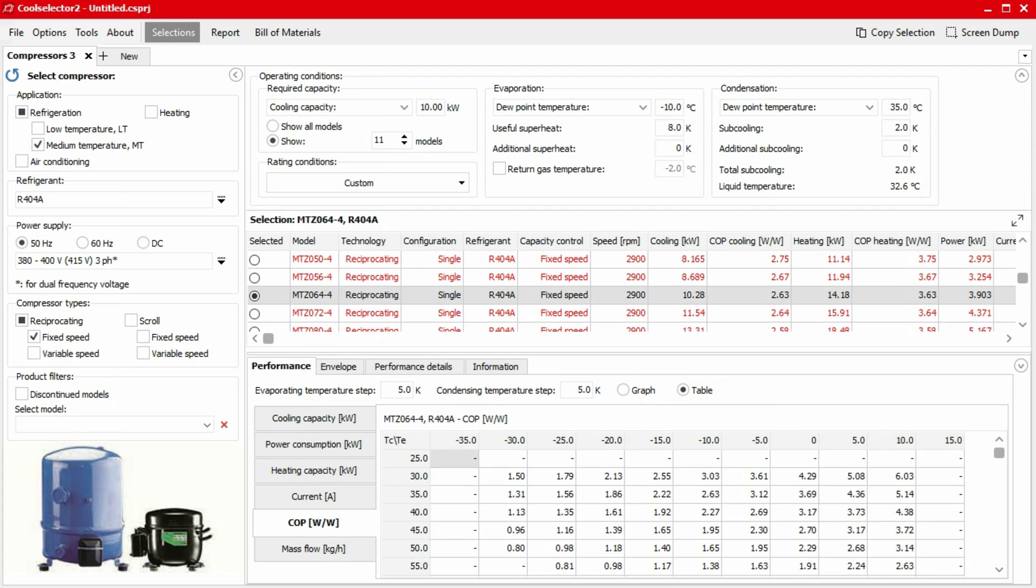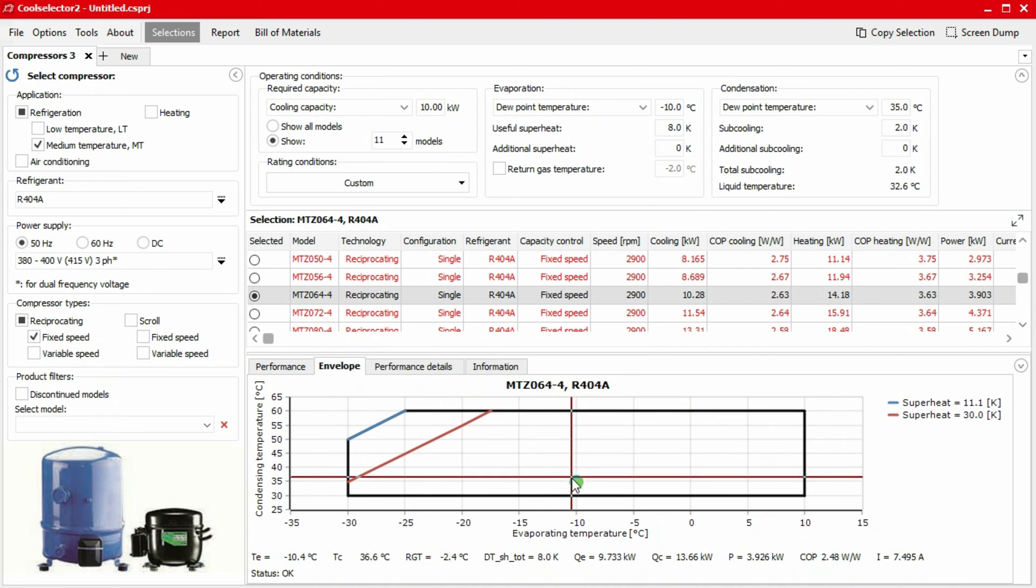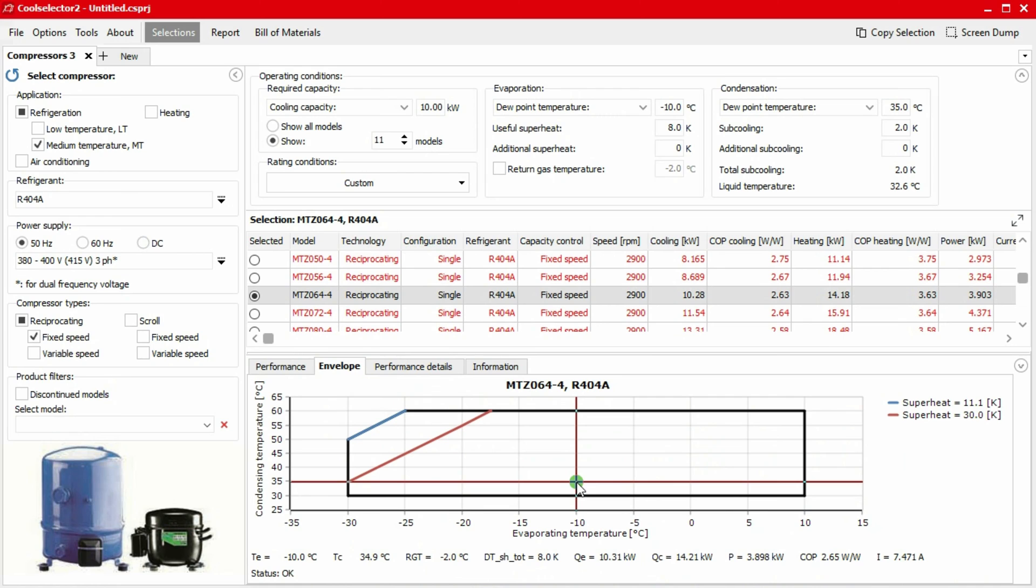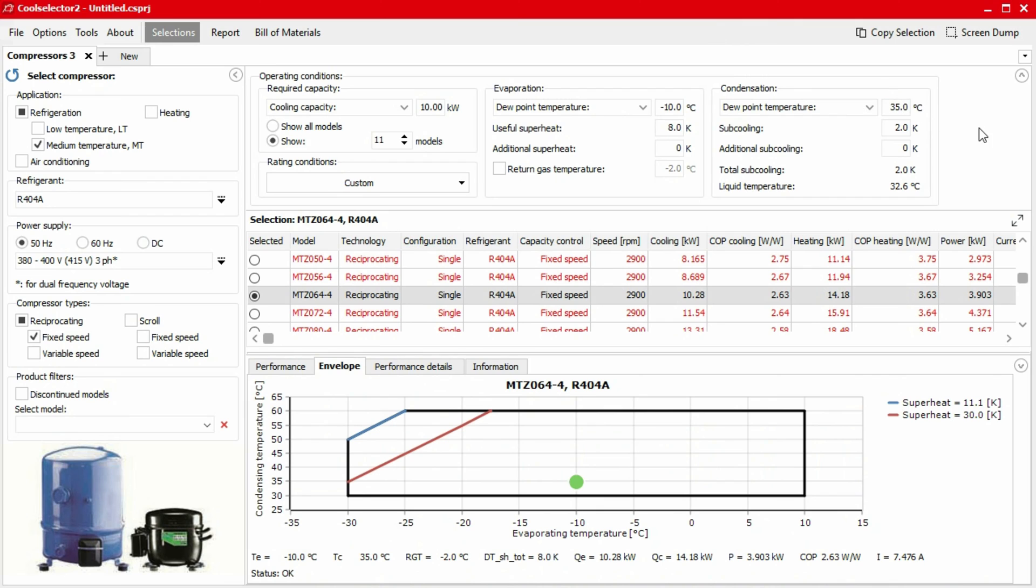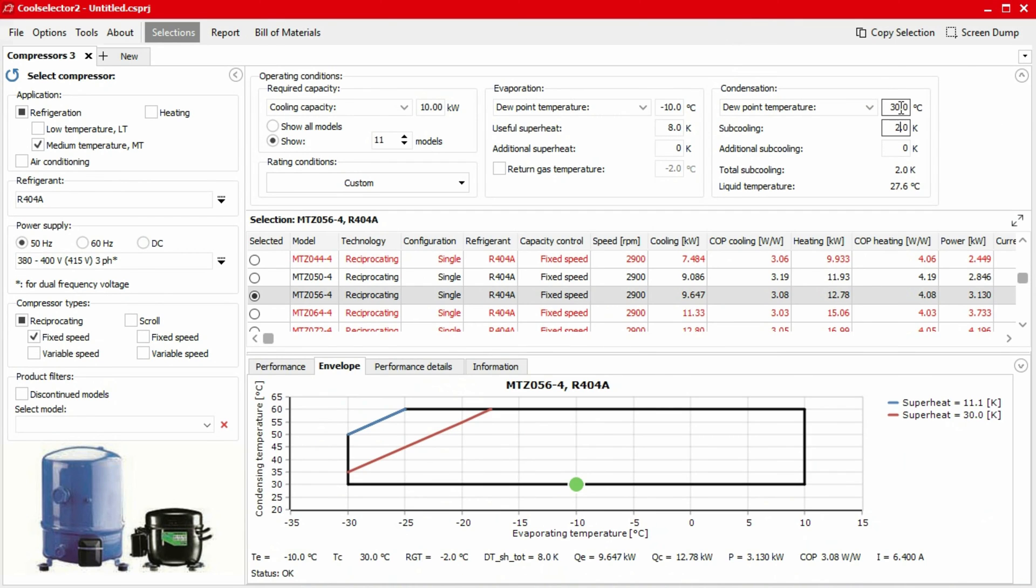If we now move over to the envelope tab, a new graph will load plotting the compressor's design region and limitations for condensing temperature against evaporating temperature. The green dot represents the compressor's position within the operating envelope according to the operating conditions we defined earlier. We can see the green dot will move if we change the values for the evaporator or condenser temperatures.